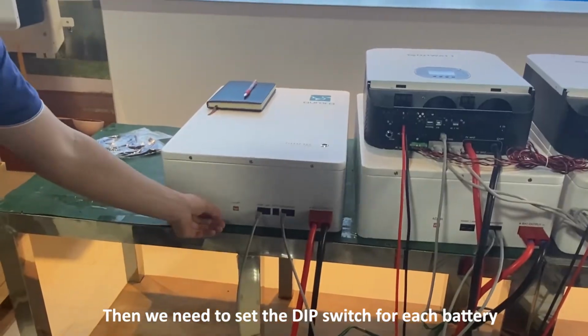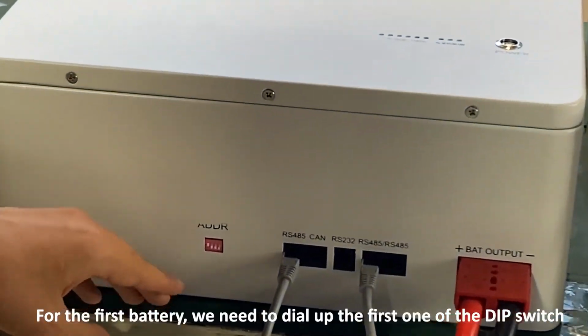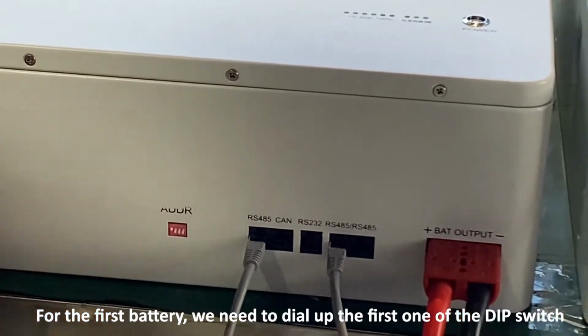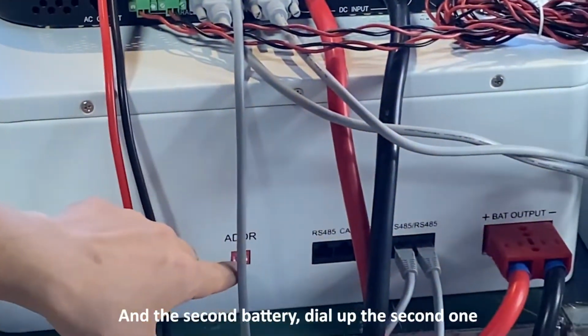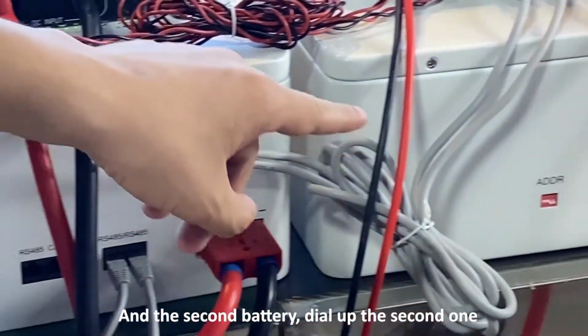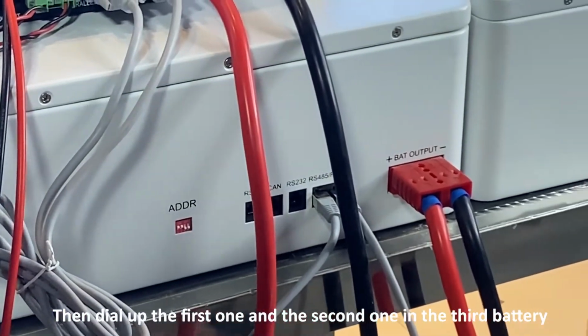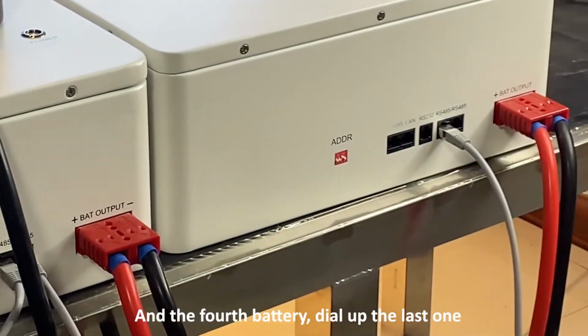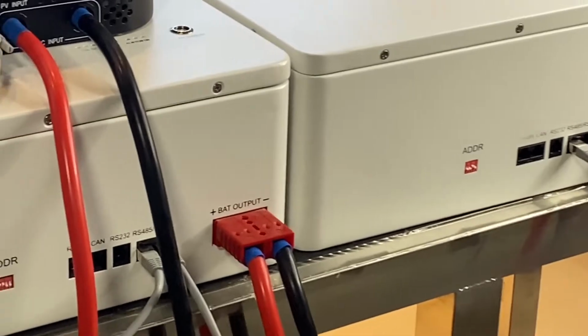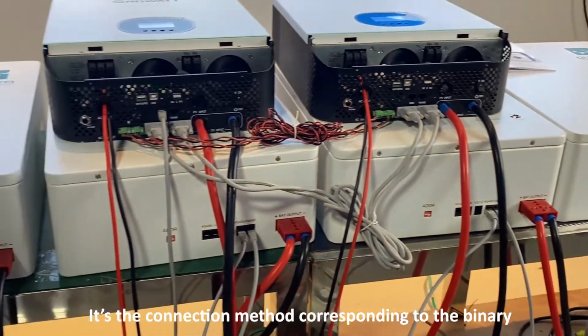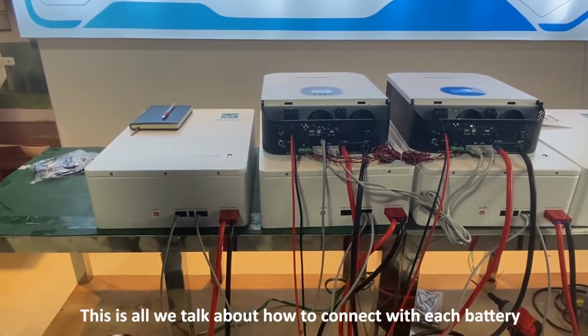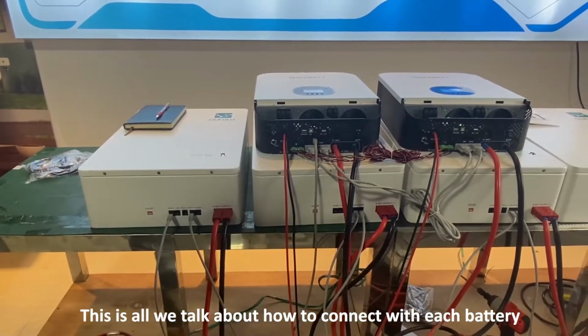At the same time, when this line is connected, we need to set the DIP switch for each battery. For the first battery, we dial up the first one of the DIP switch, and for the second battery, dial up the second one. Then dial up the first one and the second one in the third battery, and in the fourth battery, dial up the last one. It's a connection method corresponding to the binary. This is all we talk about how to connect with each battery.